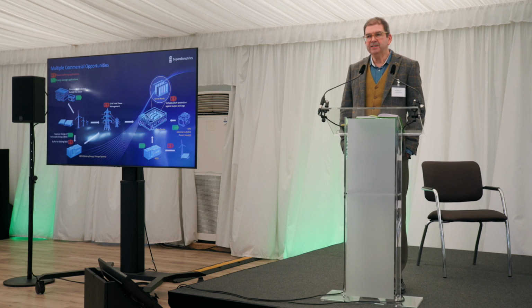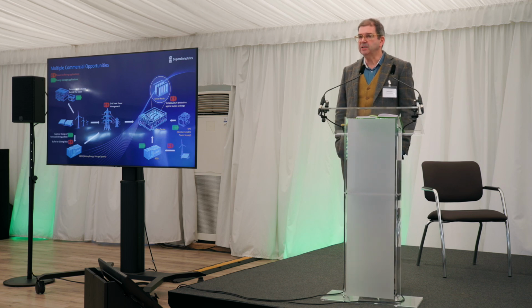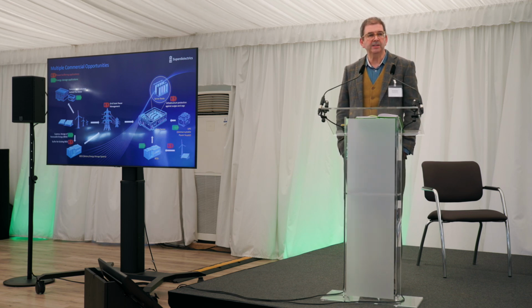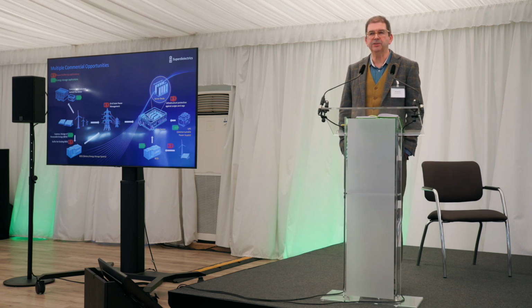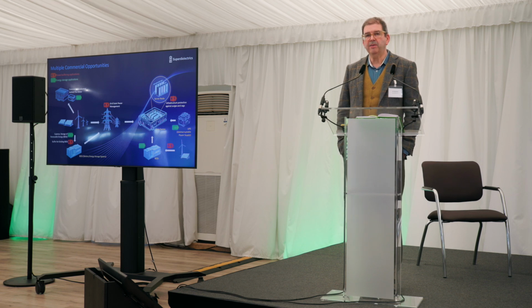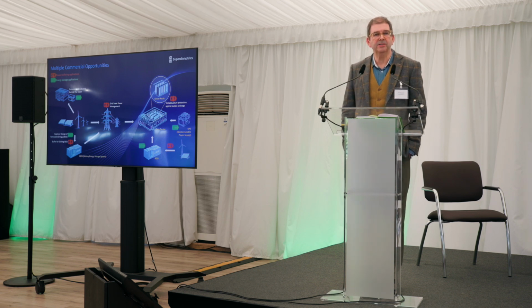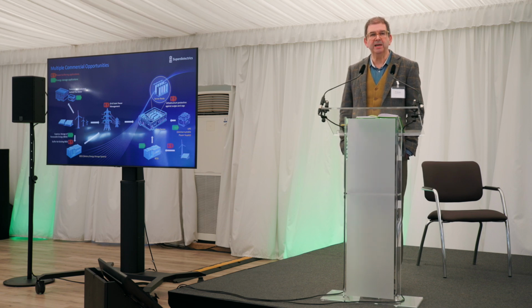So when you hit these checkpoints and power demand suddenly drops off, there's real potential for damage to the infrastructure, right down to the server rack level. So our other proposal is to use some of our zinc batteries at the rack level to cope with the sudden excess power available when the AI model enters its checkpoint phase, and supply that back to the GPUs once training picks back up.